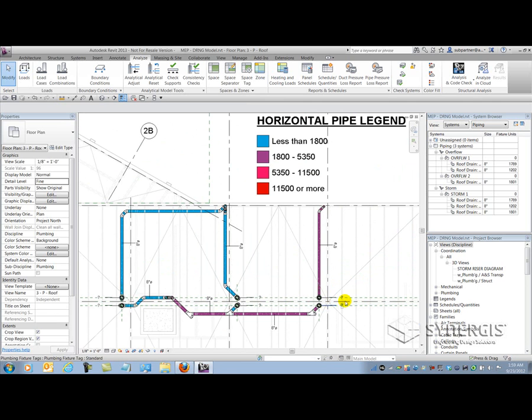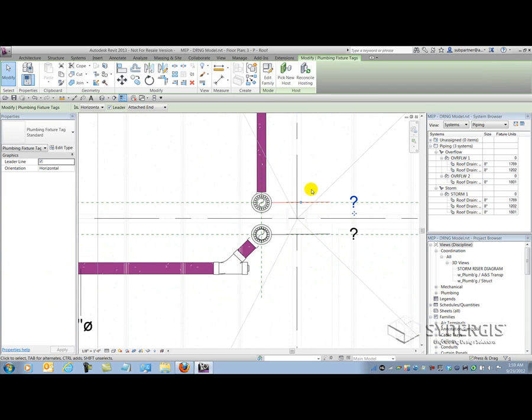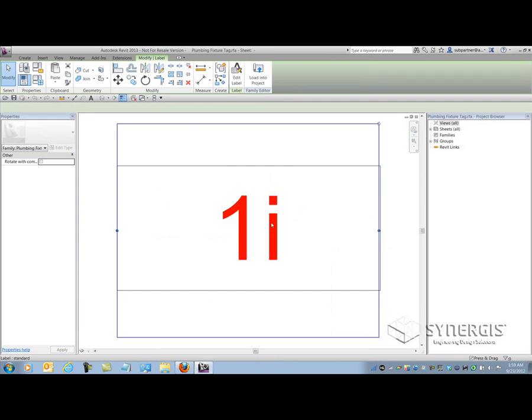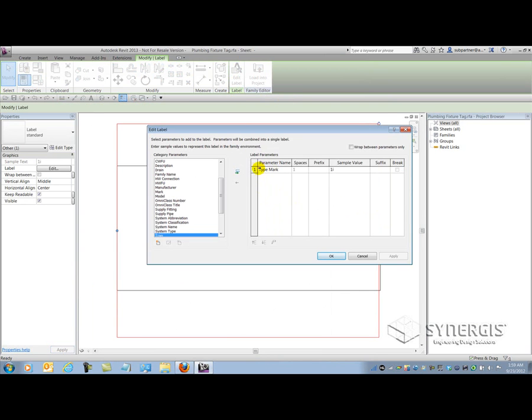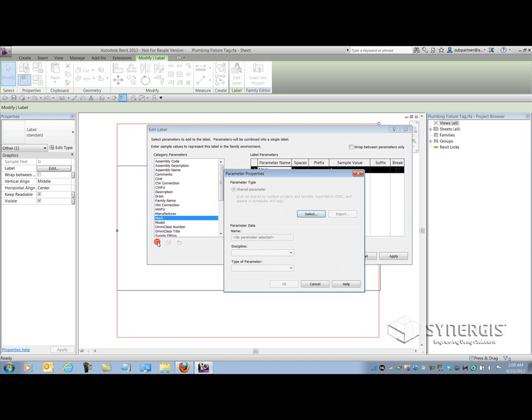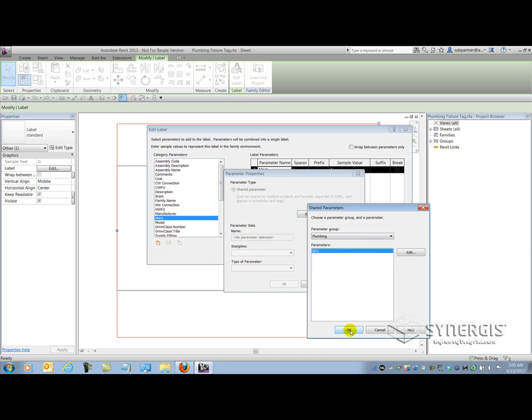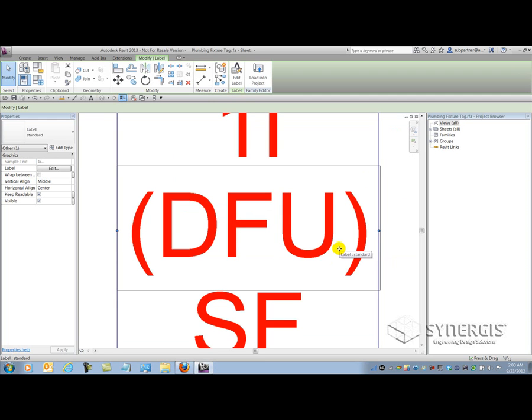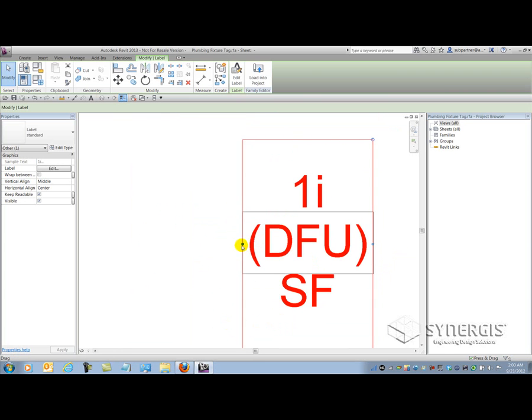Another way we can go about it is through tagging. Looking at these tags here for the roof drains, I can record or report the information regarding what the coverage is on the drain. I'll edit the tag family — it has a label in it pulling the type mark. I don't really want the type mark, so I'll get rid of that and put in the mark value. The next thing I want to do is pull up that DFU parameter, but it's not available. So I need to share it to this tag family by clicking the add parameter button, going through the process of finding the shared file, picking the shared parameter under the right group, and hitting OK. Now it's inside the tag family and I can add it. I'll put parentheses around it and indicate that this is square feet — even though technically it is fixture units.